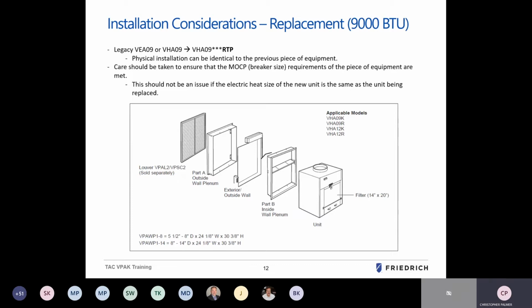Some other additional installation considerations for replacement of the 9,000 BTU unit. The legacy VEA-09 and VHA-09, moving to the VHA-09 RTP. The physical installation can be identical to the previous pieces of equipment. However, care should be taken to make sure that the maximum breaker size requirements, MOCP, on the piece of equipment are met. This shouldn't be an issue if the electrical heater size of the new unit is replacing the same size as the previous unit.